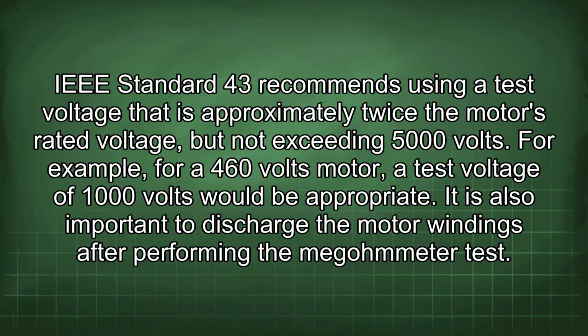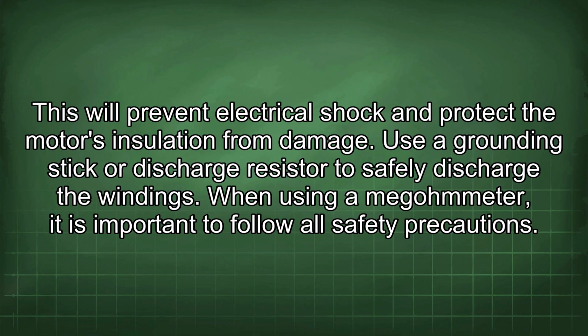For example, for a 460 volts motor, a test voltage of 1000 volts would be appropriate. It is also important to discharge the motor windings after performing the megohmmeter test. This will prevent electrical shock and protect the motor's insulation from damage. Use a grounding stick or discharge resistor to safely discharge the windings.